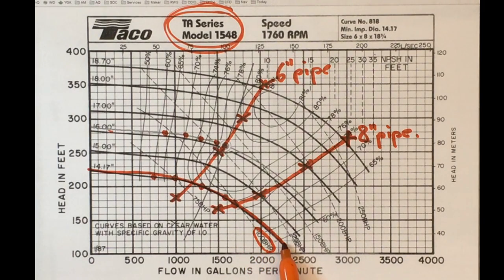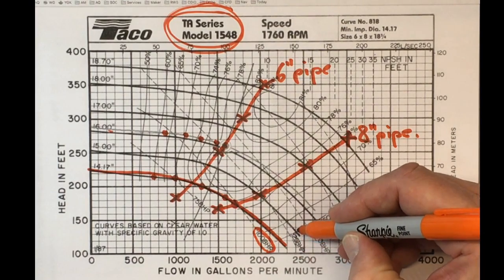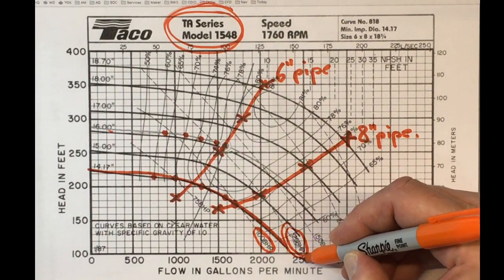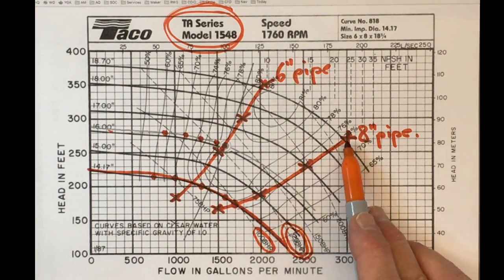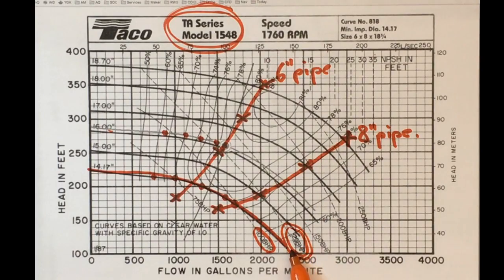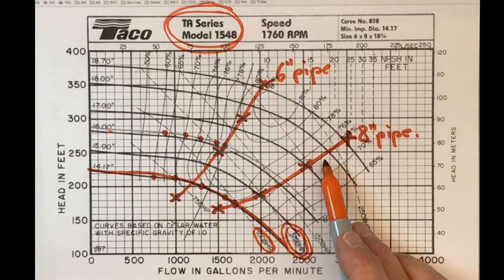So if we want to be safe, we're going to actually order it with a 125-horsepower motor. It's not going to add an awful lot of cost to the installation, but it means that if we've overestimated the losses in our 8-inch pipe, that for just a little increase in the potential horsepower of the motor, we've gained a lot of capacity in here.